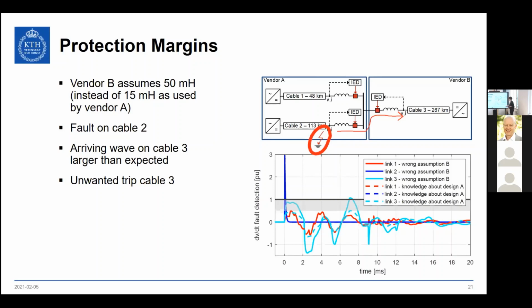If we look into the fault detection signals in a bit more detail, you can see here on the x-axis the time, and on the y-axis the dV/dt fault detection. This is again per unit normalized to threshold. So at 1 per unit we get a trip, or a fault detected and then a trip. In dark blue we can see the fault detection on the faulted cable, and that goes above threshold at time 0, very nicely, exactly as expected and required. So this circuit breaker is going to open on the faulted cable.